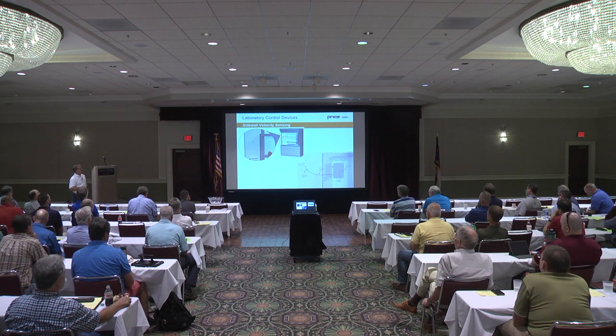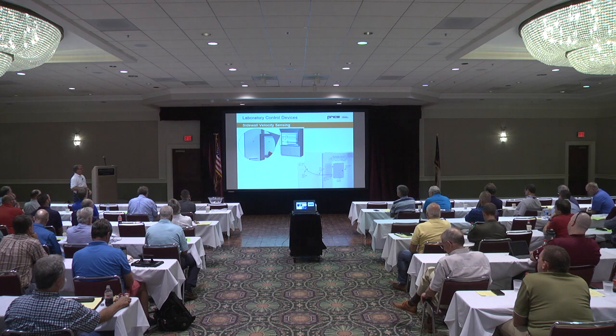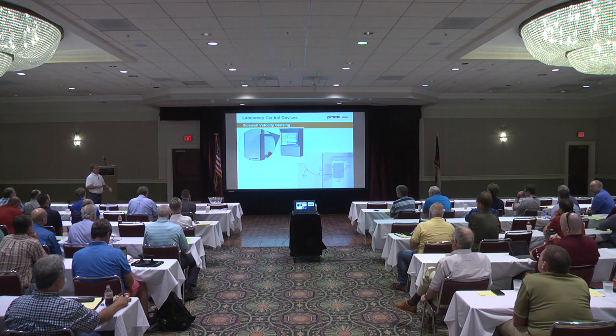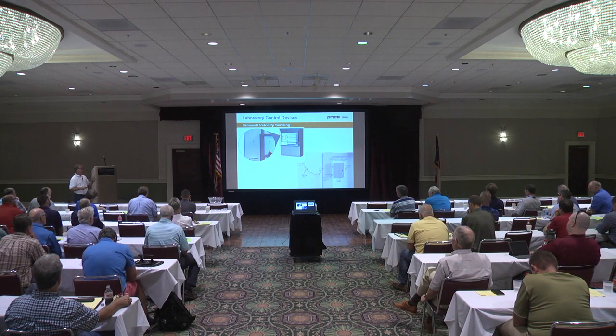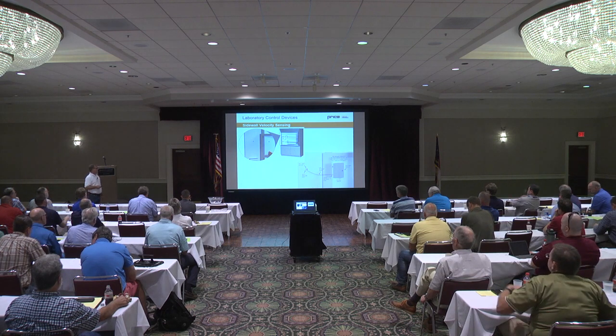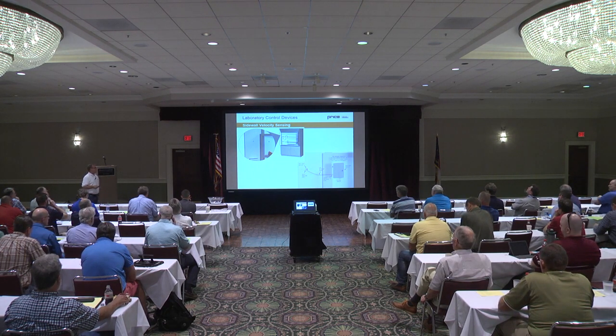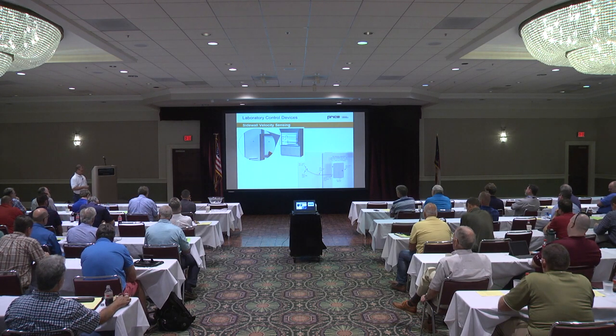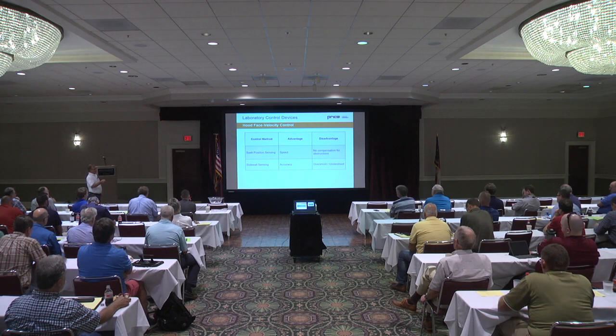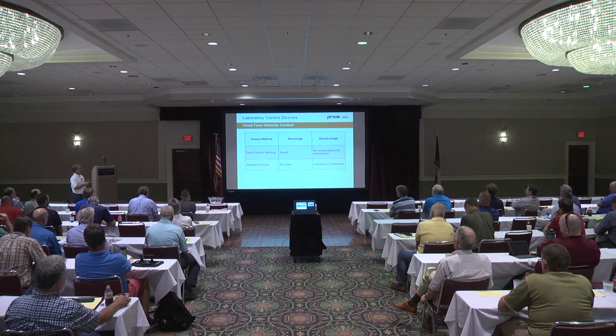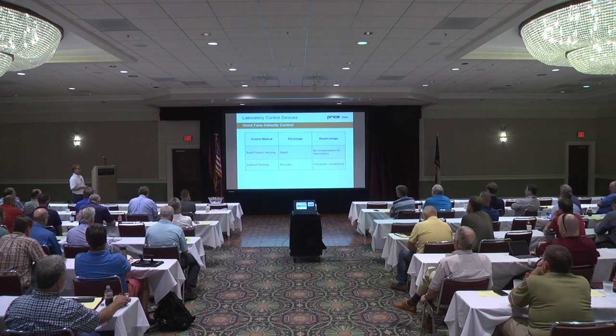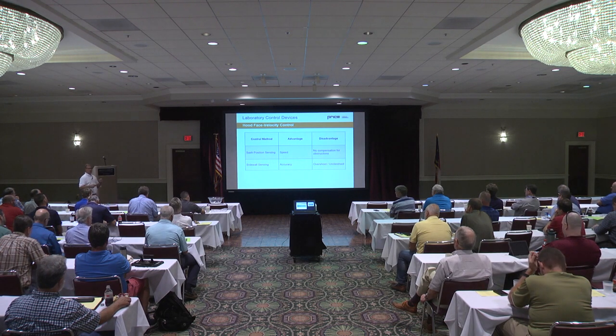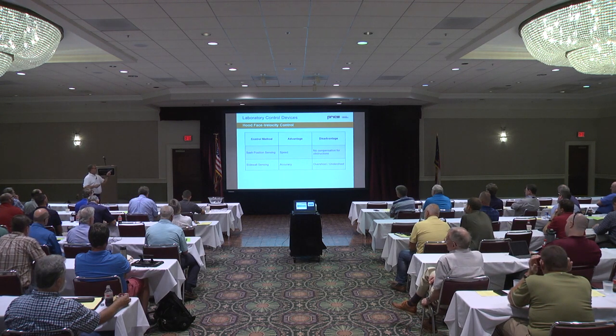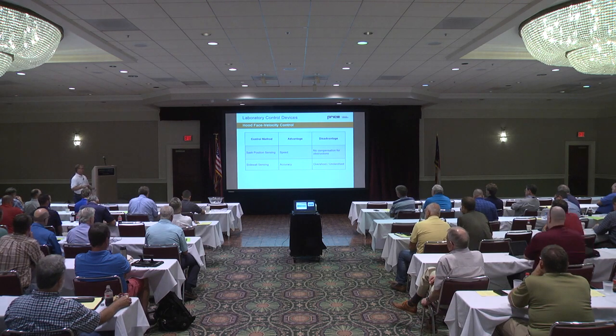So the way we deal with combination hoods, let me back up. This is just showing a way of monitoring and measuring face velocity for control, as opposed to the sash sensor on the vertical sash. You do sidewall sensing and adjust to the actual velocity reading through the sidewall sensor. So there are different control methods for hood face velocity control. Sash position sensing measures the vertical motion of the hood. The advantage is speed. As that sash is moving, you immediately know the movement of the sash, and you can control the airflow and send a signal to the valve for airflow control. The disadvantage is if there was something in the way, you wouldn't know it.